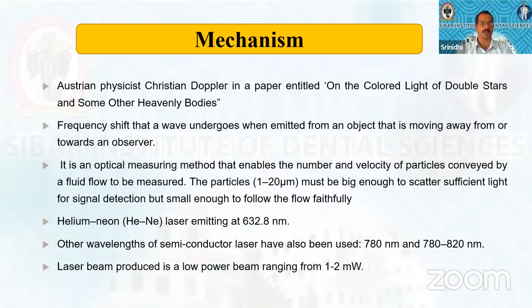The light source is a helium neon laser with a wavelength of 632 nanometer. We can also use higher wavelength to produce better penetration in the form of a semiconductor laser, that is 1 to 2 milliwatt of laser power. And this is how the mechanism is. A light is incident onto the tissue. When moving red blood cells come across this, it gets reflected, but this reflected light is frequency shifted. When the light is reflected from a static tissue, there is no frequency shift.